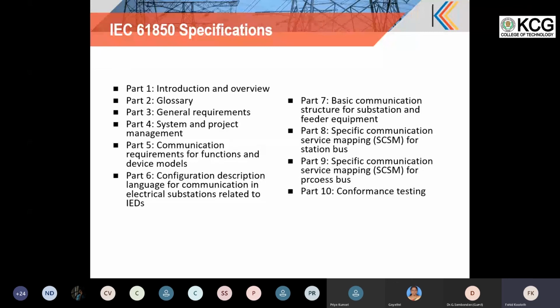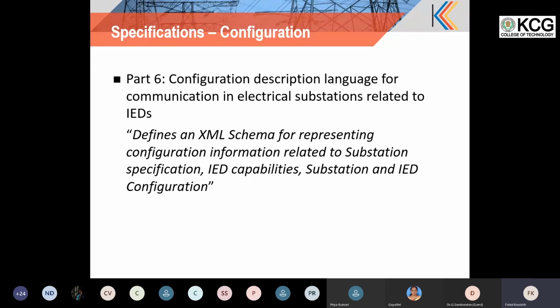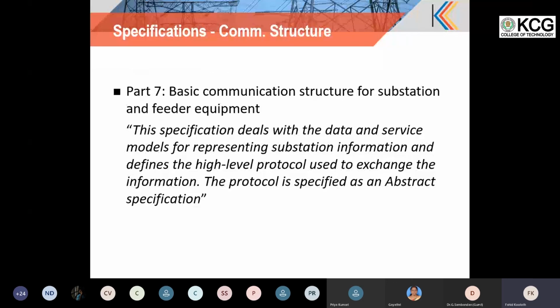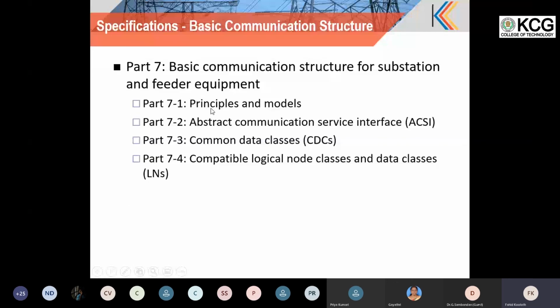Part 6 defines an XML schema for representing the details of IED capability, and the substation and IED configuration. All these details are defined in the XML schema. Part 7 defines the communication structure for substation and feeder equipment: all the data and its details, an API-like scenario, that is the functionality and data model, everything is defined in the standard under part 7. Part 7 has multiple sub-standards. 7-1 deals with the principles and models. 7-2 deals with the abstract communication service interface, ACSI. 7-3 defines the common data classes that are used. 7-4 defines the logical nodes, which are nothing but functionality and its data classes.